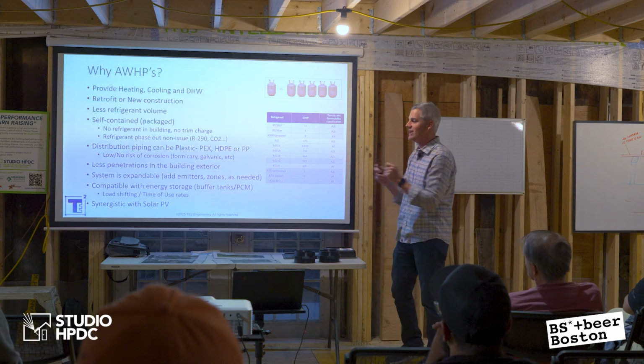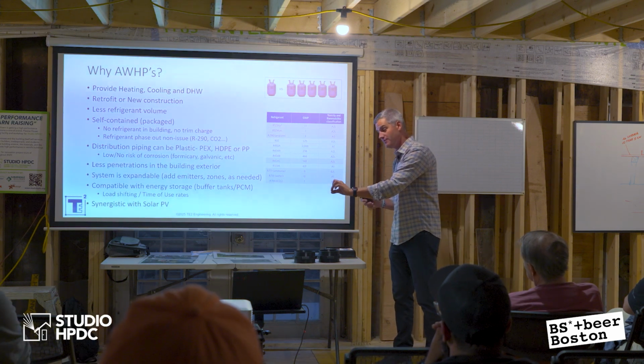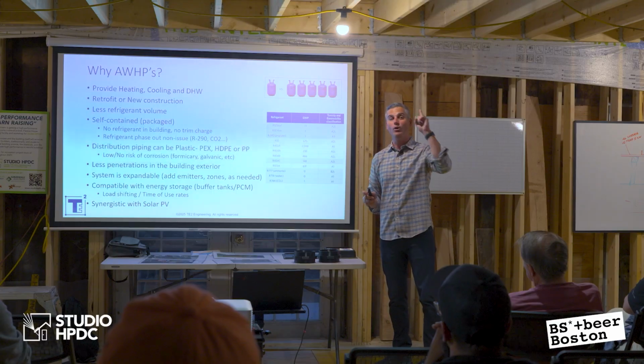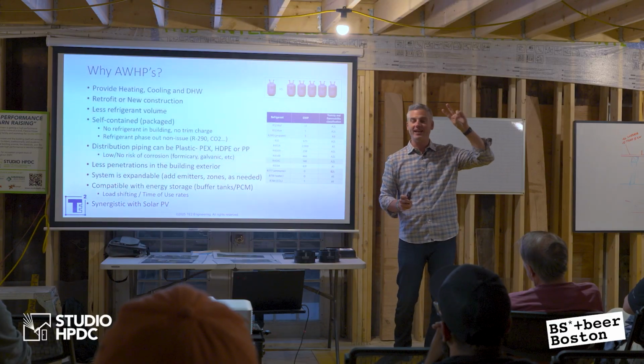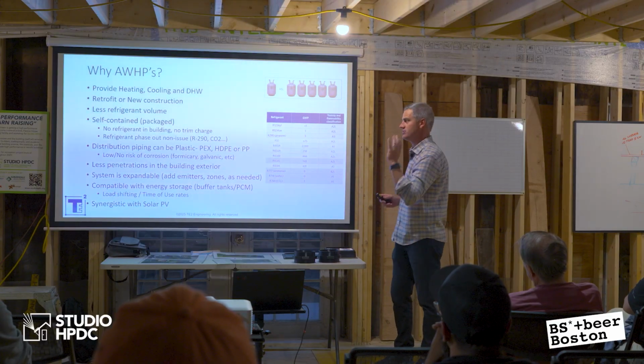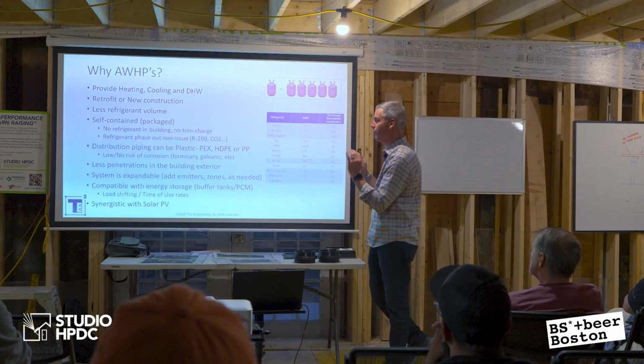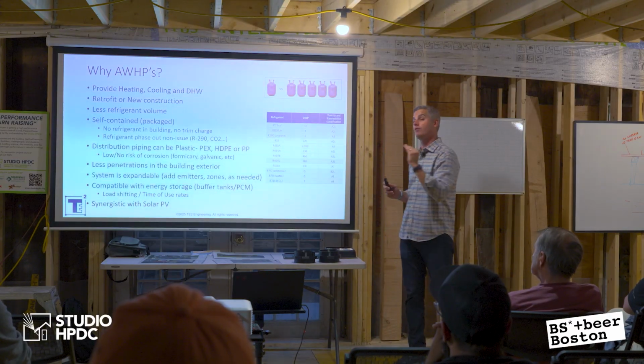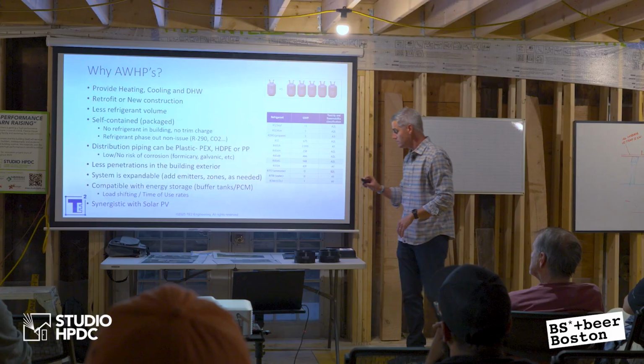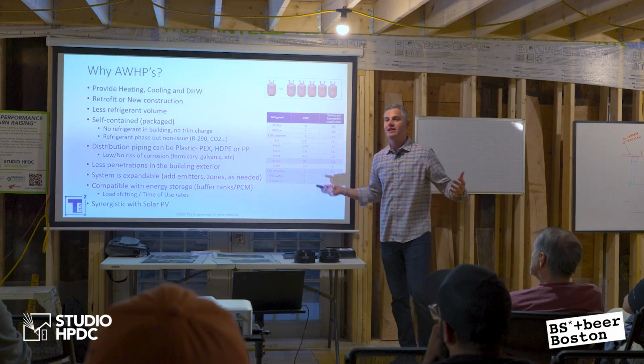I don't have to interject at all, because as soon as I hook up my gauges to it, I now have an issue. I could have moisture contamination, outdoor air getting into that system, a potential leak, a bunch of issues, right? So we want to make sure if we can avoid that, it's going to make our lives easier for the HVAC contractors as well. Refrigerant phase out. It's not an issue.